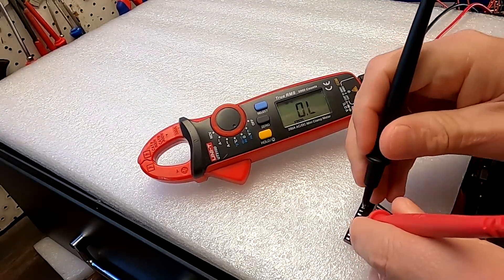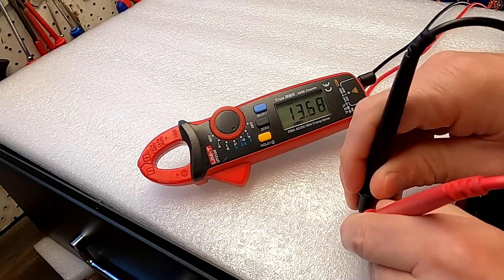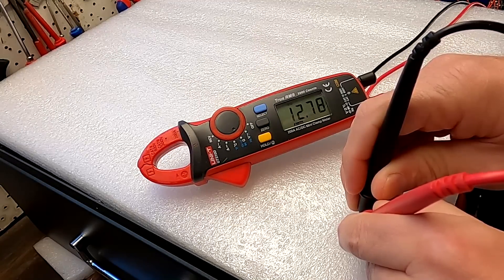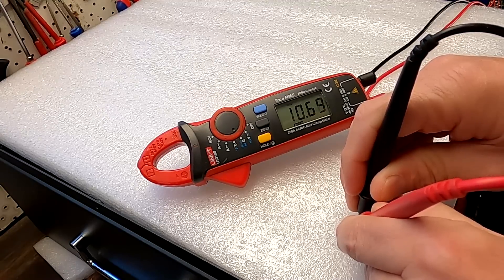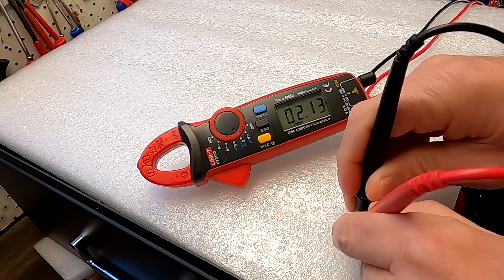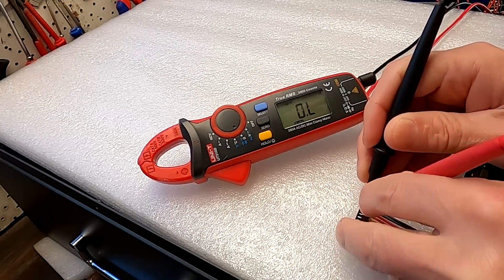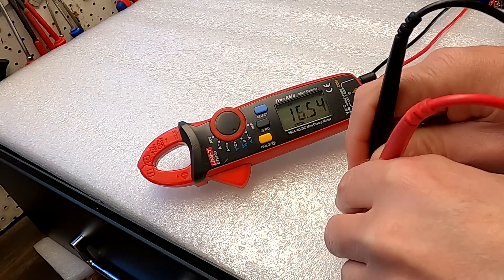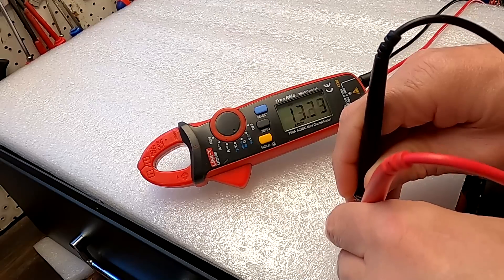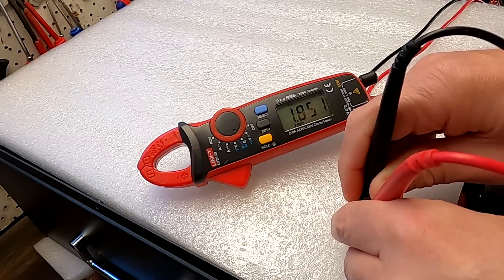I got in contact with Seplos and they sent me the instructions — it should have 10 kilohms at 25 degrees. But measuring temperature sensor number one, you can see how jumpy the resistance is: jumping between 13, 12 kilohms and down to just 2 kilohms. That's why the display is totally freaking out and showing 70-something degrees. In contrast, measuring the other temperature sensor at the end gives a constant reading — 16.55 kilohms, not jumpy at all. The faulty one is clearly jumping up and down.